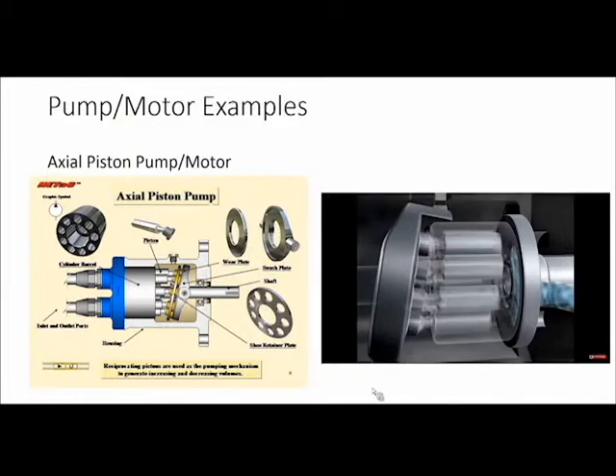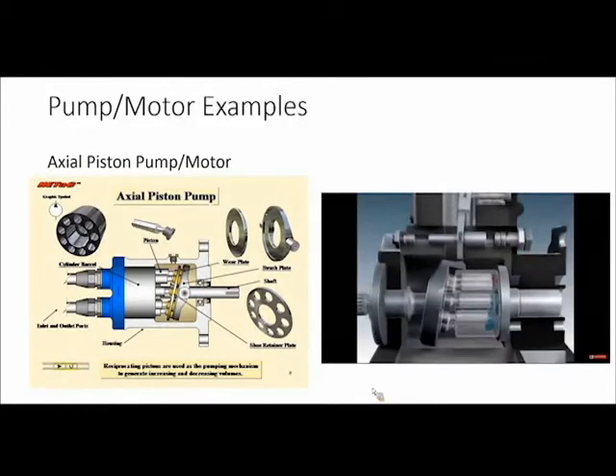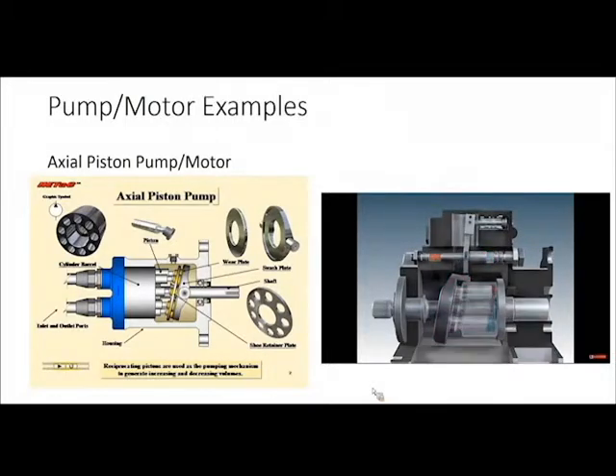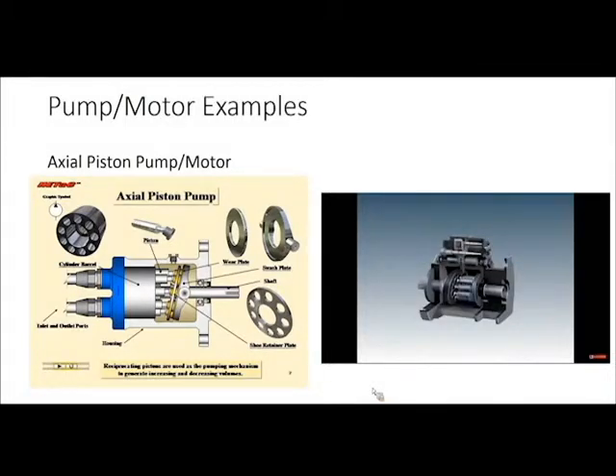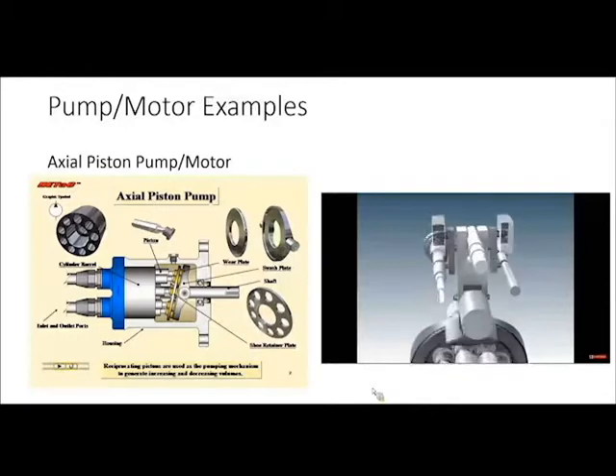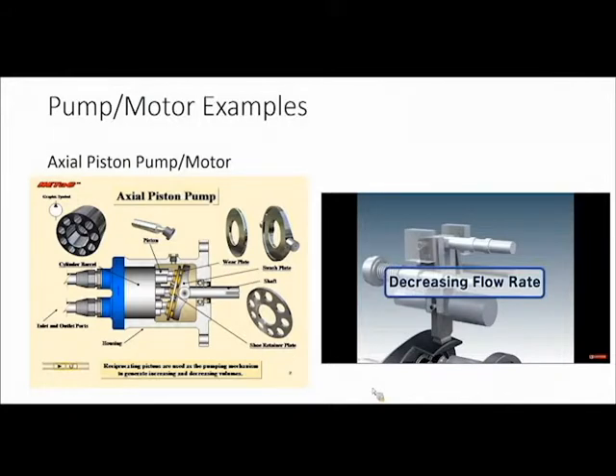In the video you can see: fluid coming in, the piston flexing, pressurizing, and then ejecting. Because of the angle, you change the displacement — therefore changing the pressure output. With a variable swash plate you can change the amount of pressurization by changing the angle. You can see how the pistons are either more or less inserted into the cylinder as you go around, and you can look at the inlet and outlet on the side and see each cylinder being exposed to the inlet or outlet as it rotates.